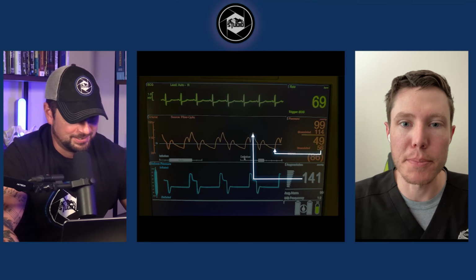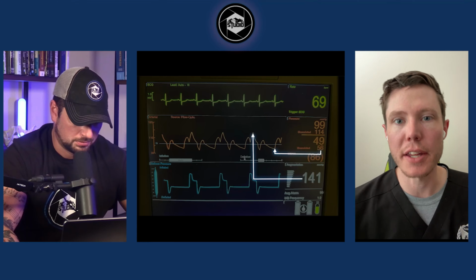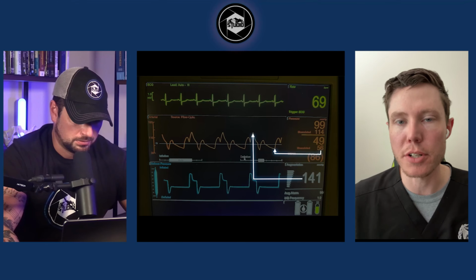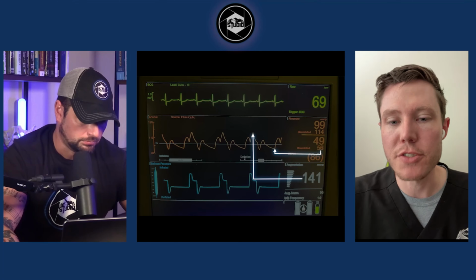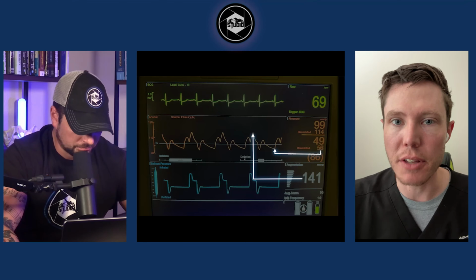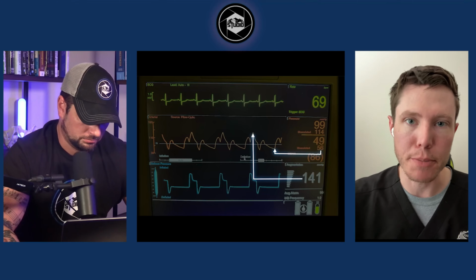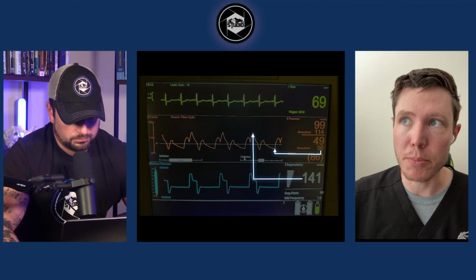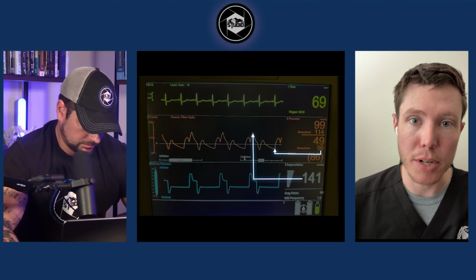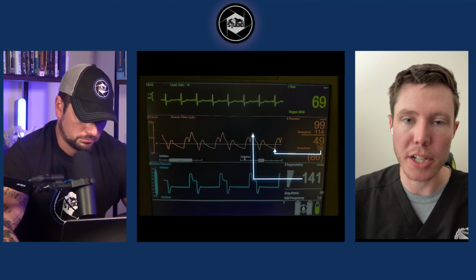Well, always follow your documentation guidelines and policies. However, I'll give a little bit of tidbit information here. The fiber optic sensors aren't really true transducers to atmospheric air, right? They have a sensor in them. They're internally calibrated, which is good, but you can't physically open a stopcock to air and zero it that way. And so while the pressures may be extremely similar and accurate, if you have a radial arterial line, that is the one that I would recommend documenting for your patient's blood pressure. Not only because that's probably the more accurate one, but also because that's the one that your distal tissues are probably seeing as well. So that's probably the better one to document.